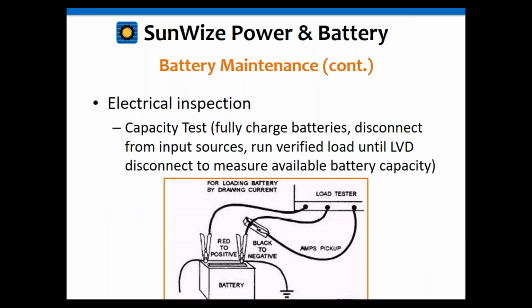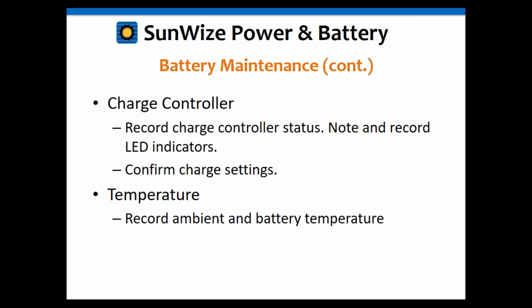If you have the luxury of being able to do a capacity test, that's great. But I know a lot of people don't have the luxury of doing that during a maintenance cycle. A capacity test is a great way to determine how much life the batteries still have, and to see where they are in their cycle life. But again, that's a luxury you may not have in the field. It's difficult to do. It's time consuming and things like that. So if it's not possible, understandable. But if you have the luxury, it's nice to be able to do that.